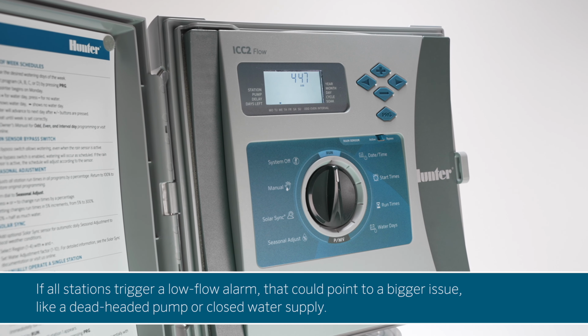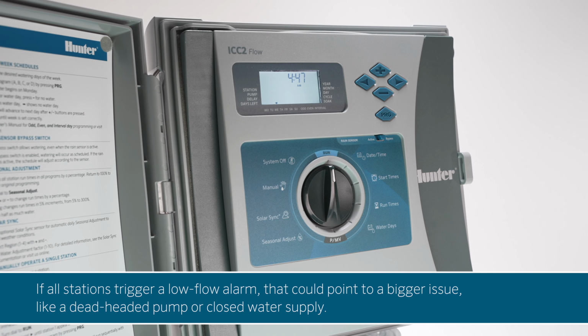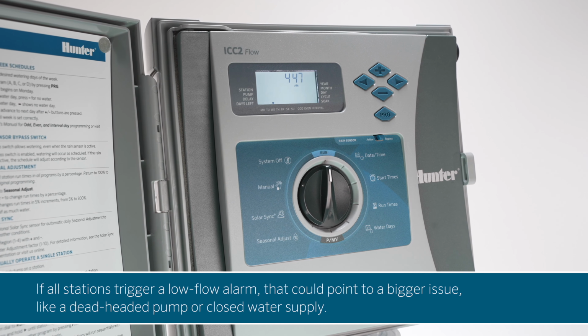If all stations trigger a low flow alarm, that could point to a bigger issue, like a dead-headed pump or closed water supply.